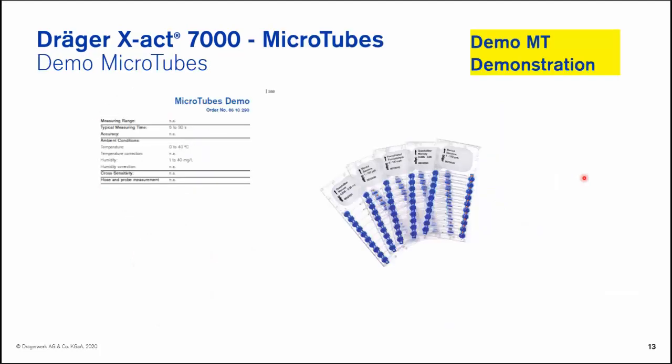I hadn't mentioned to this point, but we also have data logging. We can actually set up using the Dräger CC Vision platform up to 20 specific locations within the device which are possible for the user during the course of a measurement to select and specify that specific location and there are two lines of information available with up to 20 characters per line so you can very well define what that particular measurement location was in a given plant or otherwise. At this point in time what I'd like to do is transition to some demonstrations as to how the system operates.